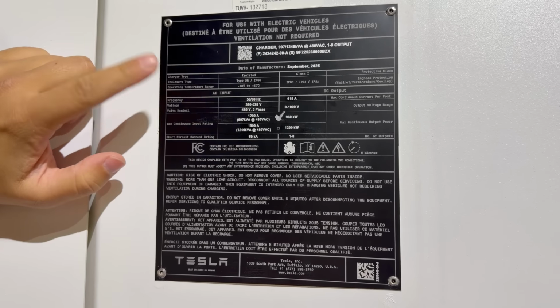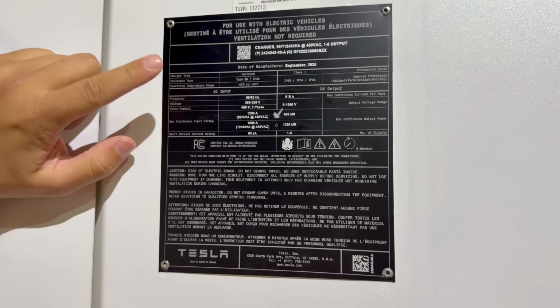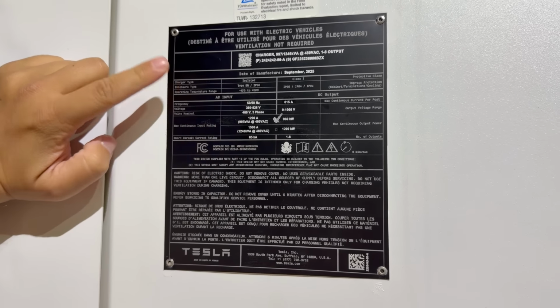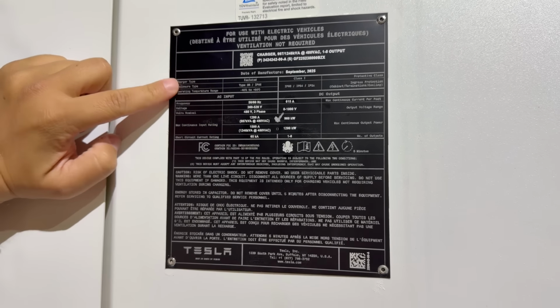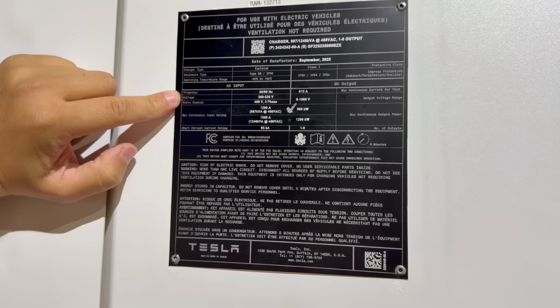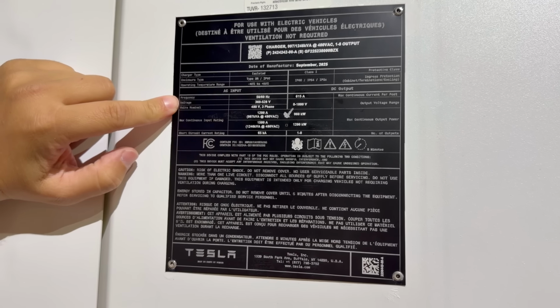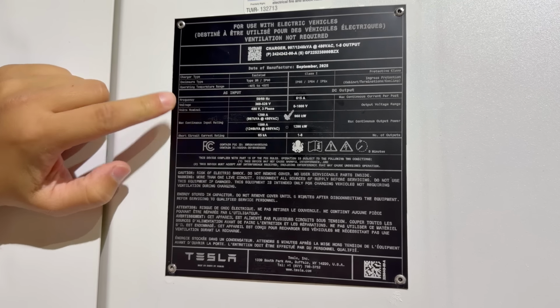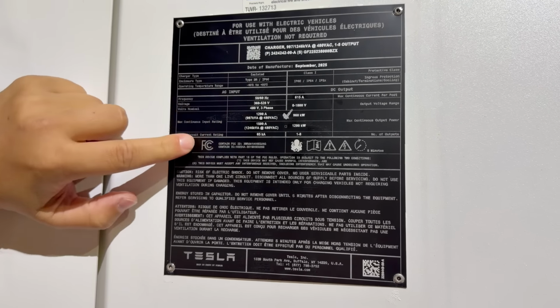Now we all know that's the operating temperature range, however Tesla can operate out of that range, typically in a derated state. So let's look at the input first. We have 360 to 528 volts. Here we're at 480 volt 3-phase. Max continuous input is either 1200 amps or 1500 amps. This one's only 1200 amp, so maybe that's an interesting configuration.